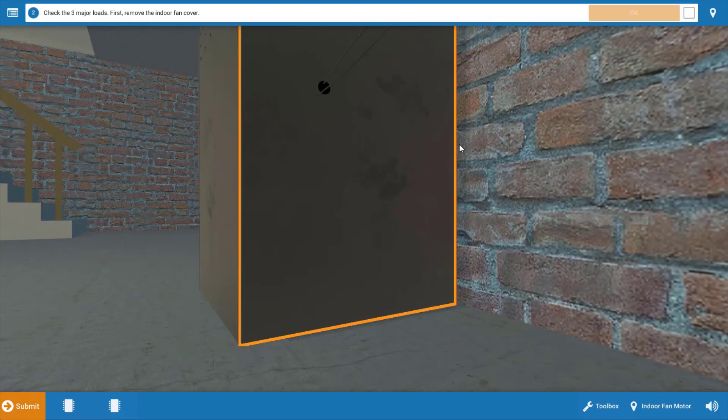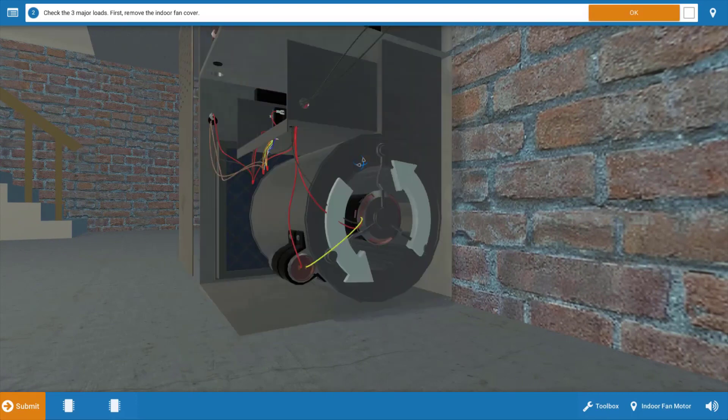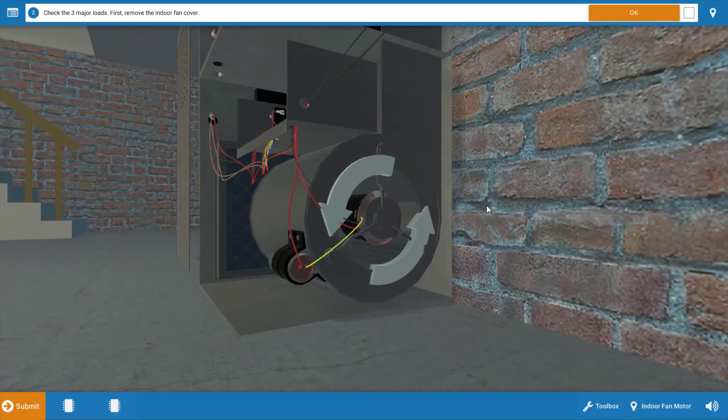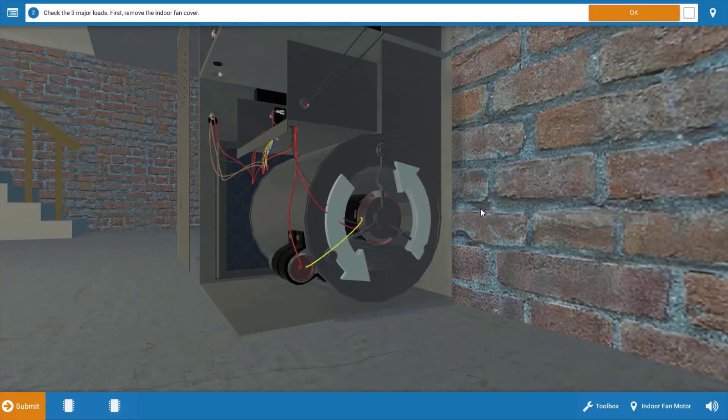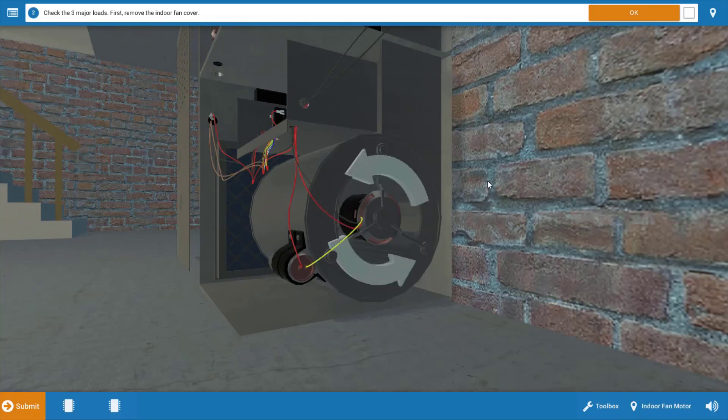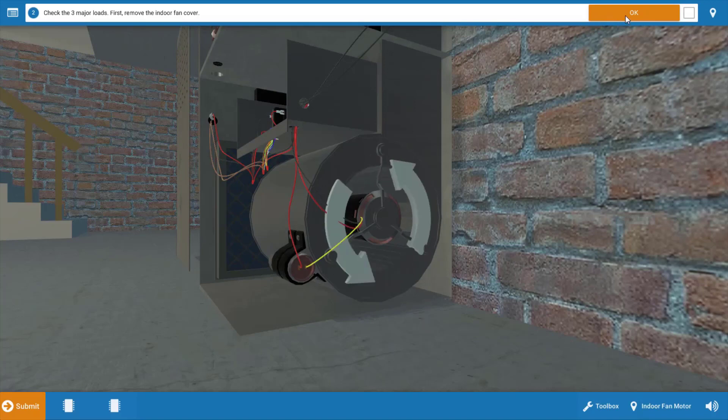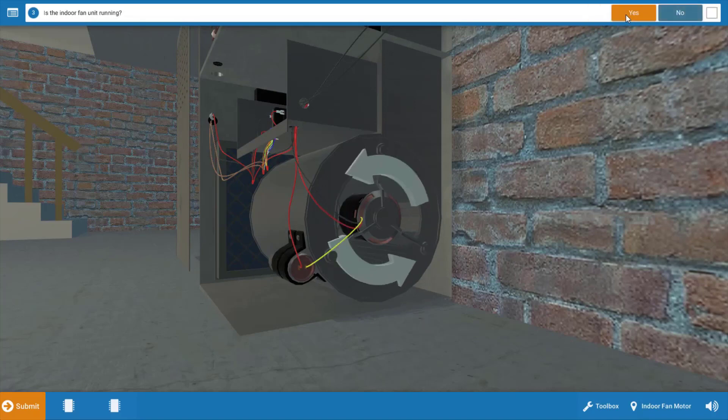Our next step is to assess which electrical loads are running. We're going to start at the indoor unit, and we're going to take the cover off, and we can see that the indoor fan motor is in fact running as evidenced by the spinning arrows. So we're going to click OK, and then yes, that the indoor fan is running.